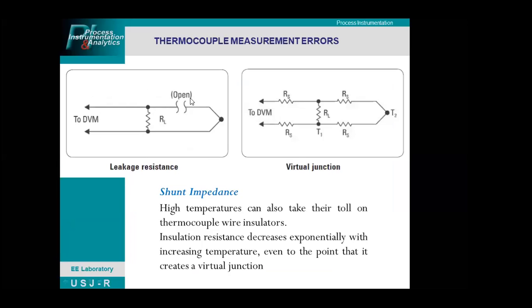There could be a leakage resistance where there's an opening here—this is the joint between the two different metals, but there's an opening, so that could be considered a leakage resistance. Then we also have what we call a virtual junction between these shunt resistances, where the two terminals are wired, combined, soldered, or welded at this junction. High temperatures can also take their toll on thermocouple wire insulators. Insulation resistance decreases exponentially with increasing temperature, even to the point that it creates a virtual junction, so now there's a tendency for leakage resistance.